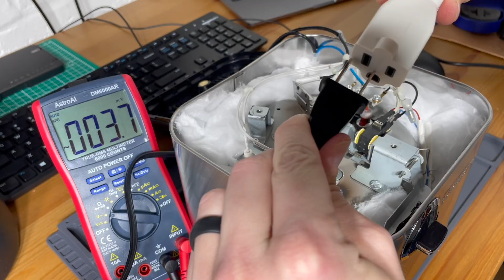All right, so we will set the meter to measure AC voltage and plug the unit in. This now has 120 volts somewhere in there, which is kind of the problem we're after, but we'll want to be extremely careful now that it's plugged in, especially since we don't know where voltage is and where it isn't. Our goal here is to determine if our missing voltage is concerned with the wiring coming to the switch, or with the switch itself.